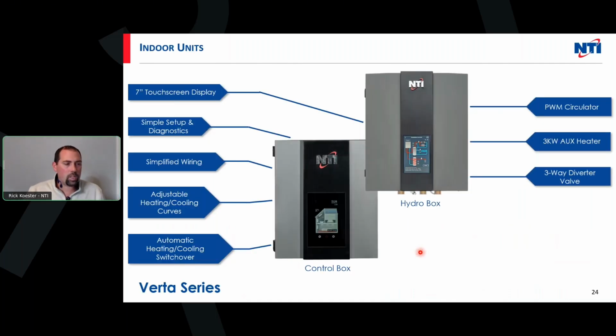Some features on the indoor unit: 7-inch touchscreen, simple setup and diagnostics, simplified wiring, so we give you that nice single location to bring all your inputs, outputs, adjustable heating and cooling curves, which we'll talk about, and automatic heating and cooling switchover on the control box and hydro box. Specific to the hydro boxes, we have a PWM circulator inside and a 3 kW auxiliary heater for supplemental heat. This is standalone, meaning that we power this separately from the control, and we'll talk about that once we get into some of the wiring. And there is a factory 3-way diverter valve installed as well, and we'll see the inside of that in a few seconds, and you'll see how well insulated everything is.